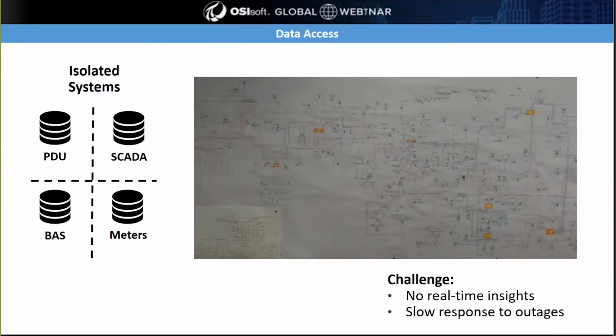We have PDUs, or primary power distribution units, that have their own monitoring systems. If you have on-site generation, a local SCADA will house the data. Automatic transfer switches and uninterruptible power supply data typically live in building automation systems. And finally, there's often a standalone power monitoring system containing consumption and power quality data from electric meters and submeters across the campus.